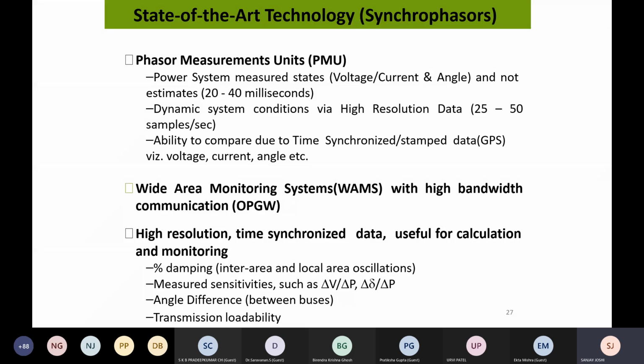PMUs provide the ability to compare data due to time synchronized and sampled measurements, comparing voltage phases and current phases measured across the network. For example, across a line with two voltages at either end, because the data is time synchronized and stamped, you can compare the voltages at the two ends of a line, and also compare the angles. That is the real strength of wide area measurement systems, the ability to measure angle difference across a line or corridor. That is a major advantage of PMUs and wide area measurement systems.